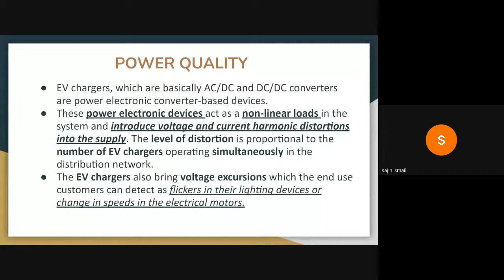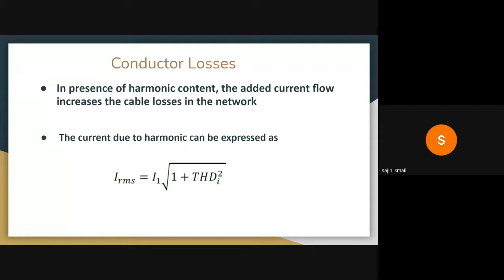So I hope that you all are well aware of the harmonic content and the calculation of it, how we calculate the harmonic content of a particular harmonic frequency and all. I'm not describing much about it. Now, the conductor loss due to this harmonic current. A distortion factor comes in the current, and this distortion factor creates an additional current, which will definitely become a loss. It will be an additional loss on top of the existing loss. So you can see the increased current leads to an increase in conductor losses. As the total harmonic distortion percentage increases, the loss will increase. It's a natural thing to happen.